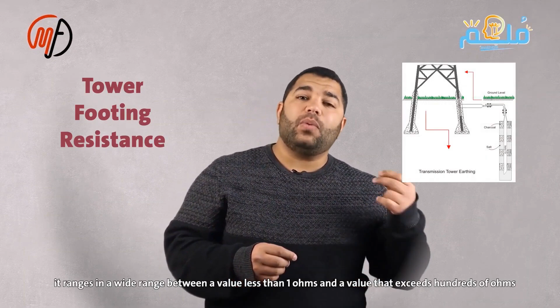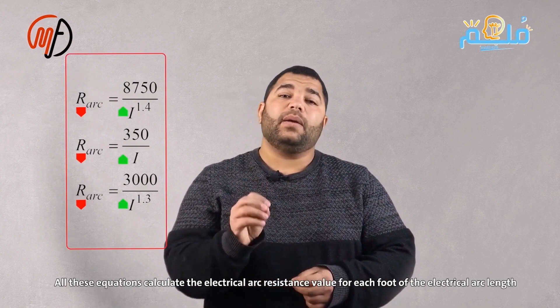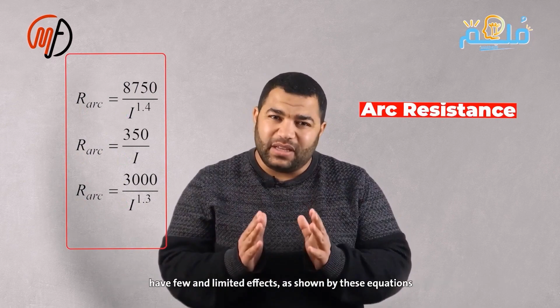As for the resistance resulting from the grounding of the towers, it varies widely, ranging from less than 1 ohm to values exceeding hundreds of ohms. The resistance of the arc is calculated using one of these approximate equations, and all these equations calculate the arc resistance in ohms per linear foot of the arc length. It's important to note that the higher the fault current, the less significant and limited the effect of the arc resistance, as is clear from the equations.